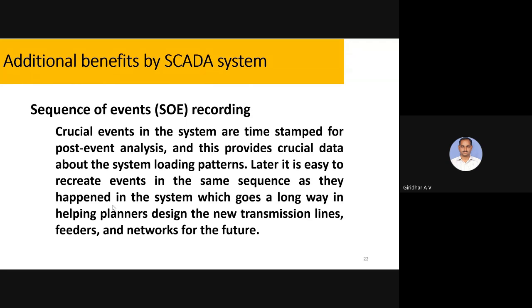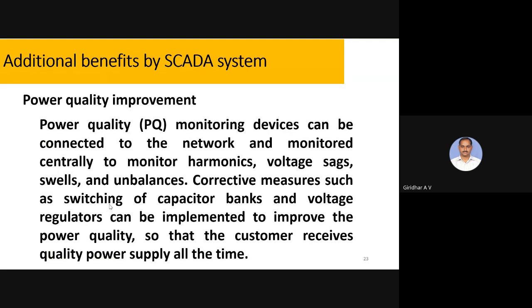So we can do sequence of events recording, everything. Time stamping: whenever any fault occurs, from that point onwards there is a change from normal. That can be analyzed properly with time stamping, at what time it occurred, what type of devices were there, and in what way the particular fault came to picture. All this can be analyzed very properly with sequence of events recording. It will be very helpful to take appropriate actions, and we can get load patterns, everything.